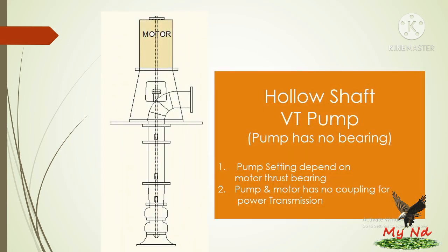In that picture, we are looking at a hollow shaft motor, so it is called a hollow shaft VT pump. In that type, setting depends on the motor thrust bearing. The pump and motor have no coupling for power transmission. In that, a common shaft is used for power transmission.